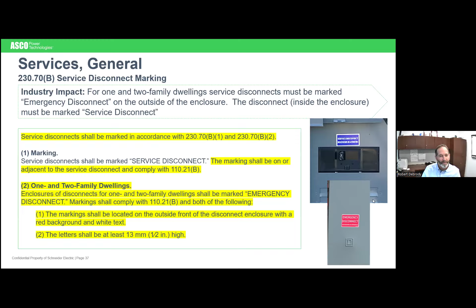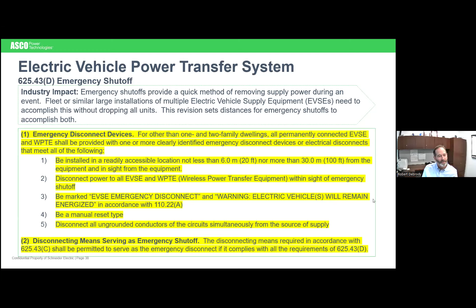Electric vehicles and the powering of electric vehicles and charging them up. So this does not apply to 1 or 2 family dwellings. This is where facilities that charge up multiple electrical vehicles. And they're really looking for an emergency shutoff. They want that emergency, and they go into details here in the paragraphs talking about where they want it located. They just want to make sure they can quickly turn off power in case there's a problem. You know, they want it no less than 20 feet to the actual location of the vehicles being charged up, and no more than 100 feet within line of sight. And it will be clearly marked. So good idea. I guess this is part of the evolution of electric vehicles becoming more and more of a presence here in the States.